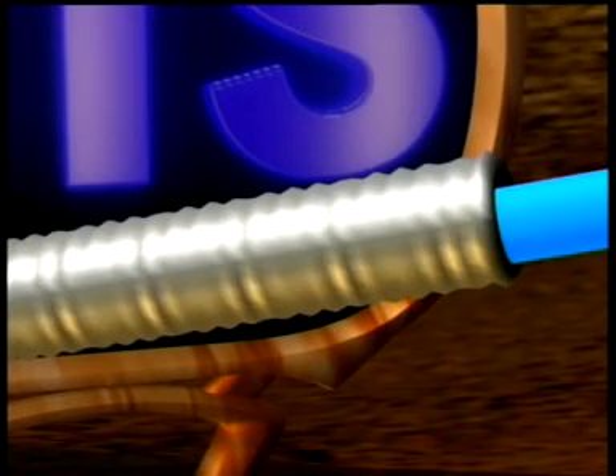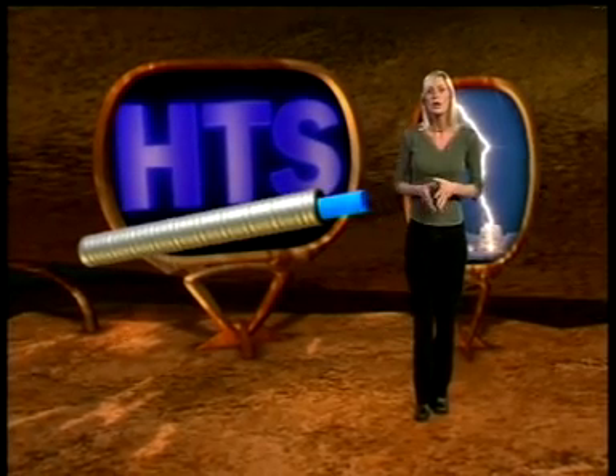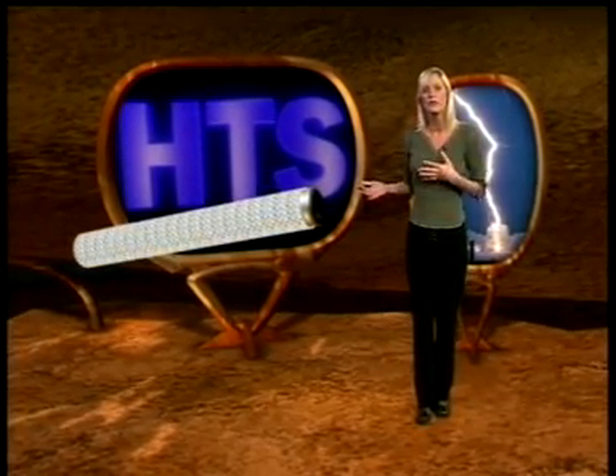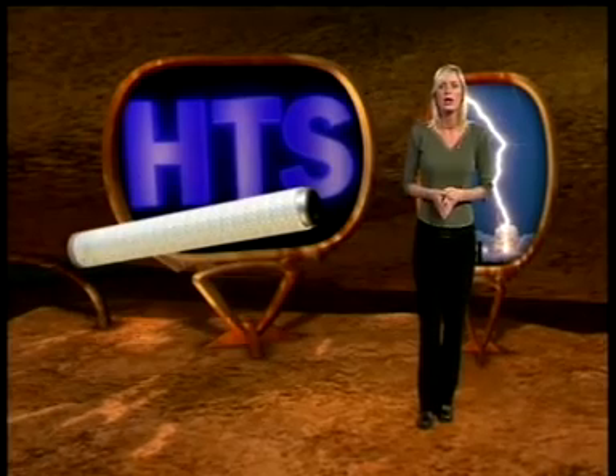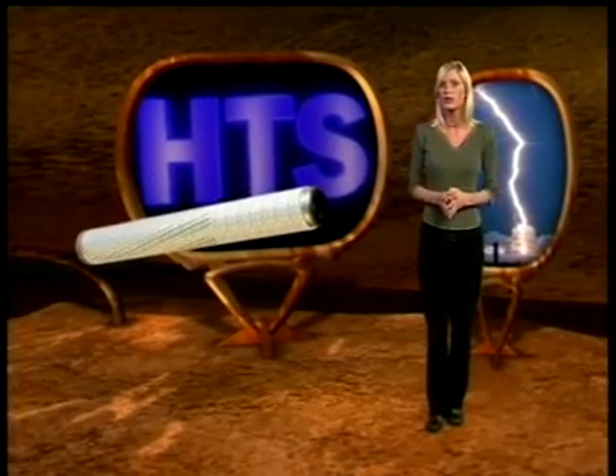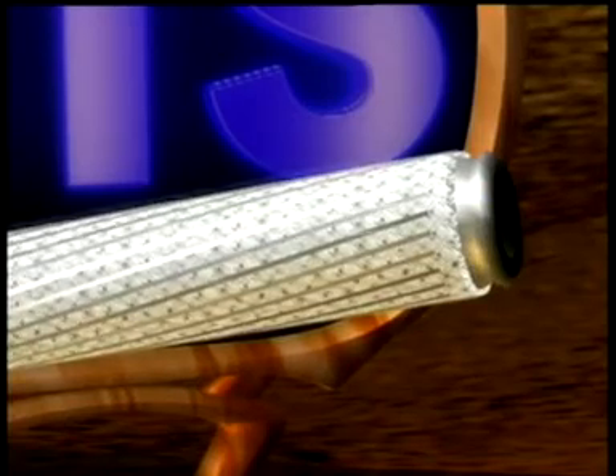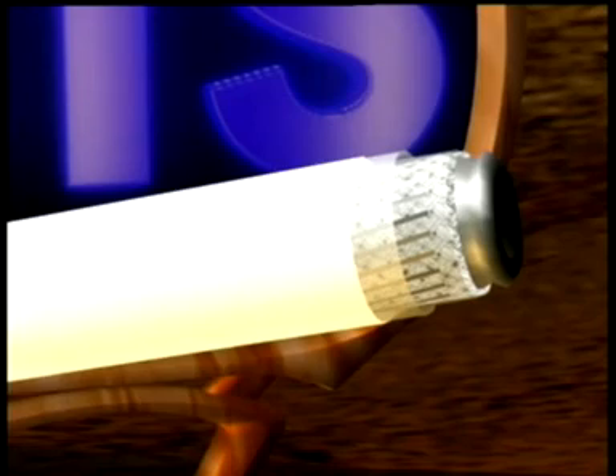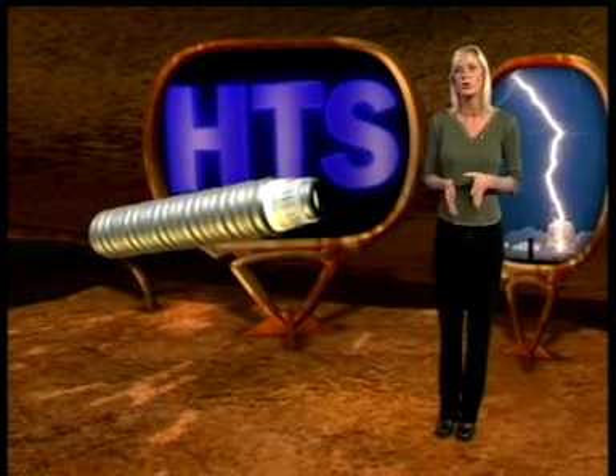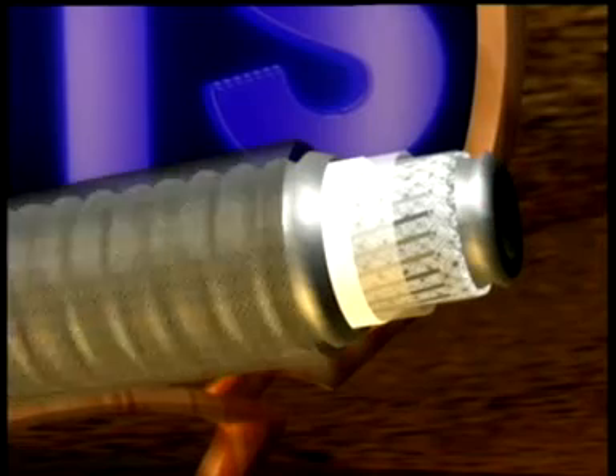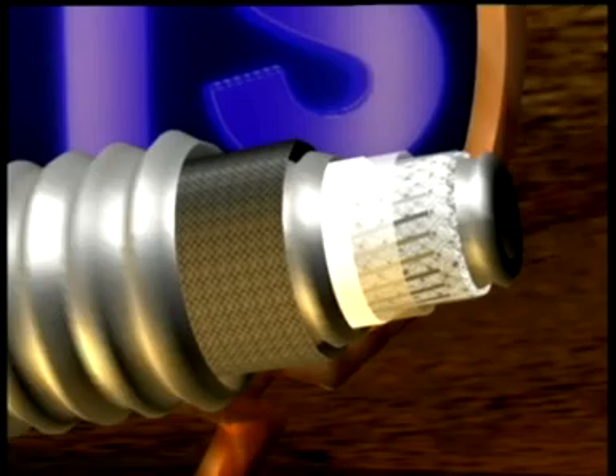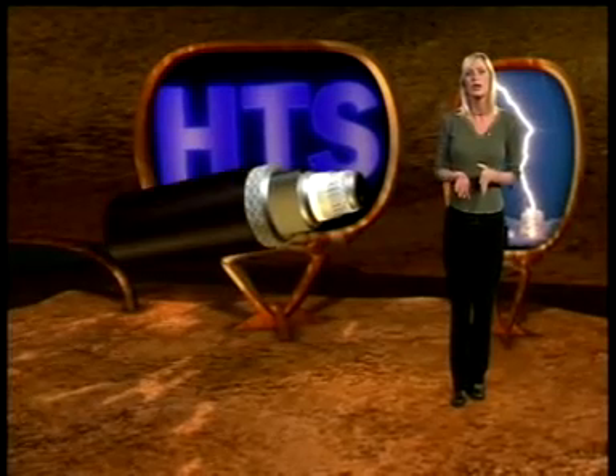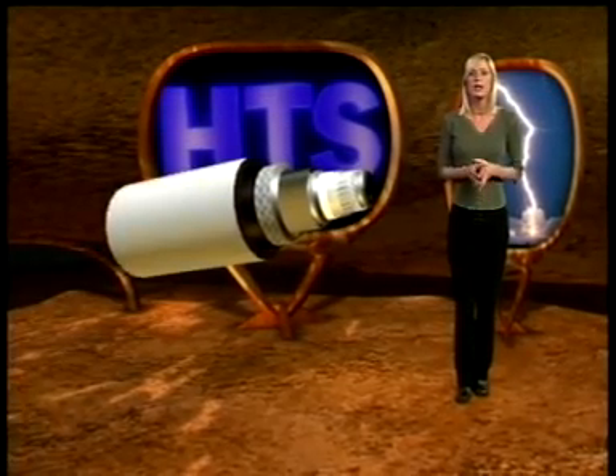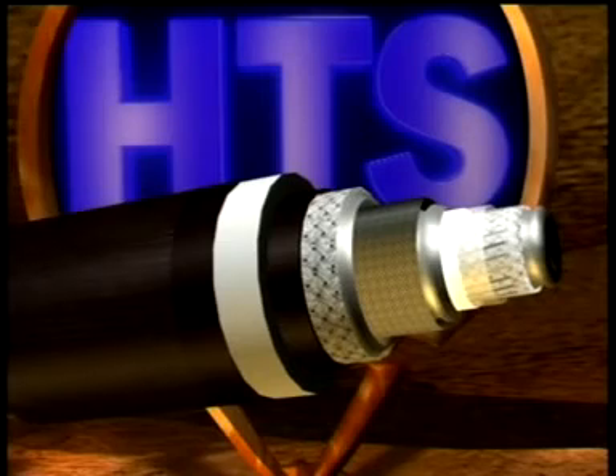This cold liquid nitrogen is circulated through the center of the cable to keep it cold. The superconductors themselves are in form of tapes from another NKT company, Nordic Superconductor Technologies, or NST. Outside the tapes there's a layer of thermal insulation with metallic foils called super insulation. Outside all this, there's electrical insulation and protection layers. They're based on reliable elements and have been known to NKT for a long time.